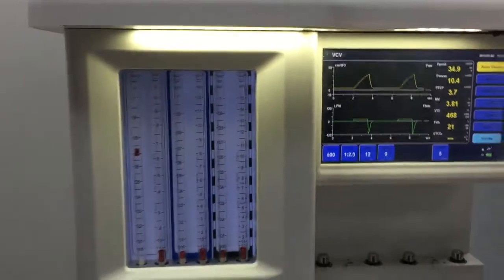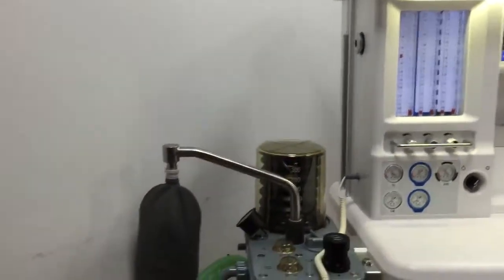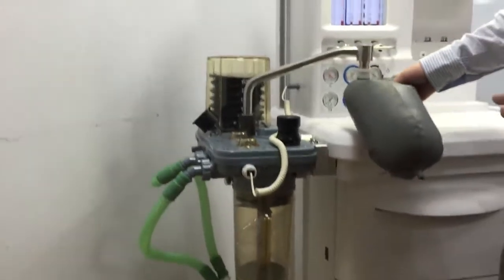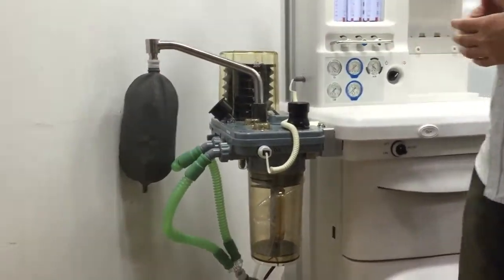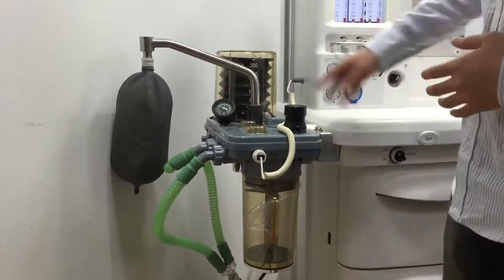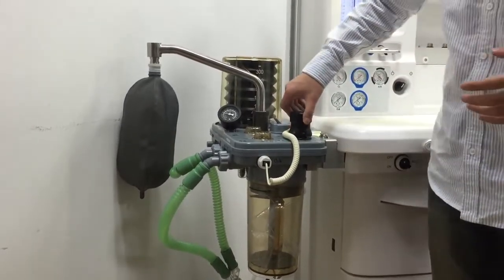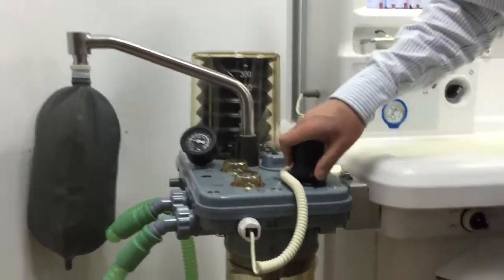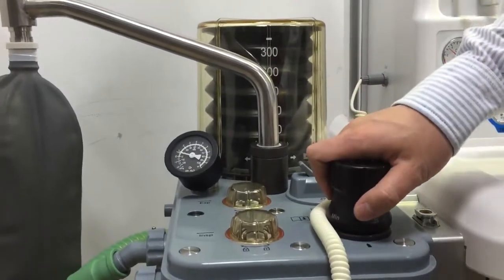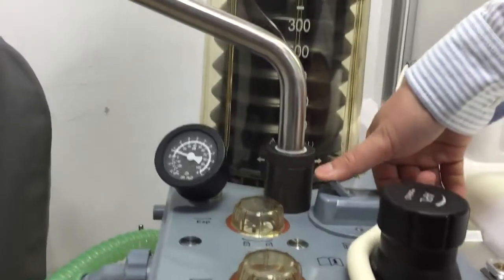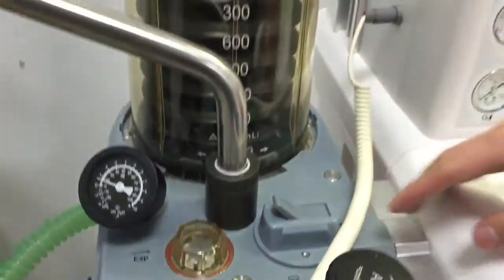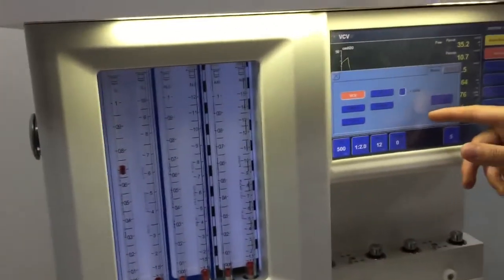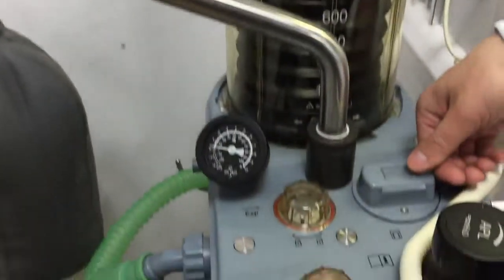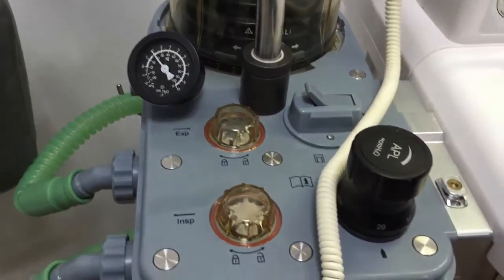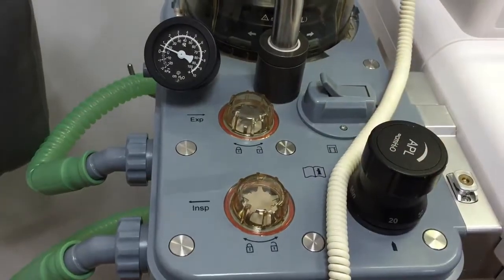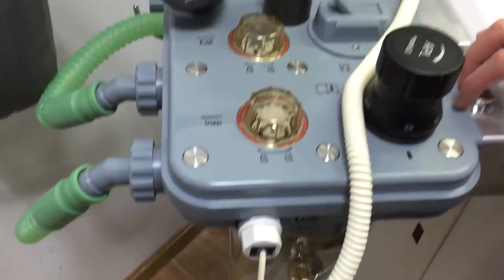Okay, so we talk about the absorber system. There's nothing special for the bag arm and support arm, and everything is there. Also the pressure gauge, adult bellows, and APL valve, where you can feel the click. Even if I close my eyes and want to shut it, I can do so because of the click. And one key switch for manual and automatic, so I don't need to switch to manual here and then touch to select the manual mode, because I can simply switch it to get manual mode. Convenient. And the inspiratory check valve and oxygen sensor are all standard here.